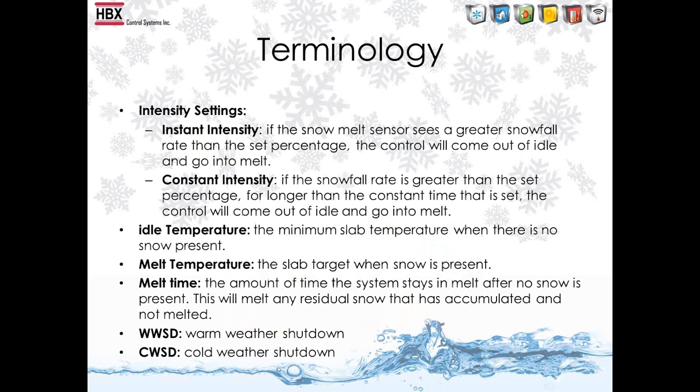Here are some of the terminology we use when talking about the HBX snowmelt systems. We have two different intensity settings. Instant intensity is when the snowmelt sensor sees a greater snowfall rate than the set percentage — the control will come out of idle and go into melt. For example, if you have a client that doesn't want to see any snow on their driveway, you can set the control to approximately 5 or 10%. If you have a client that doesn't mind having an inch or two on the driveway, you can set the control to 30 or 40%.